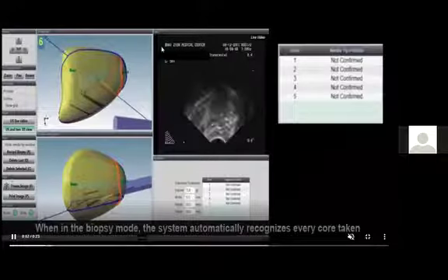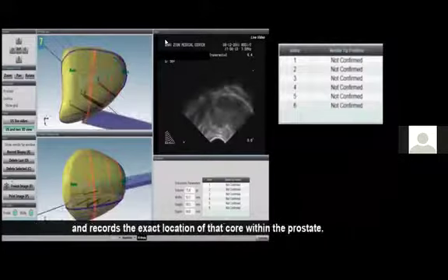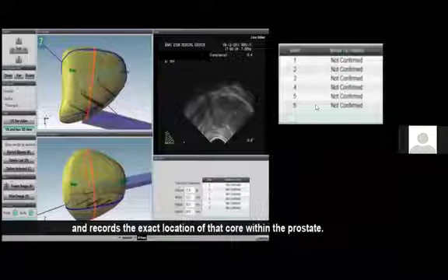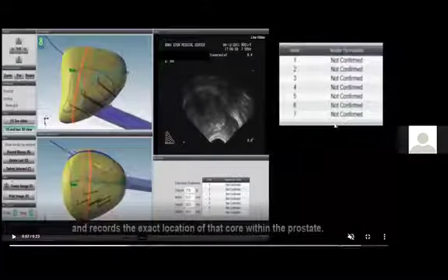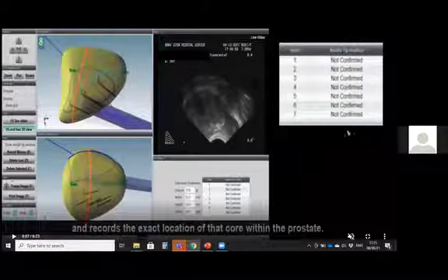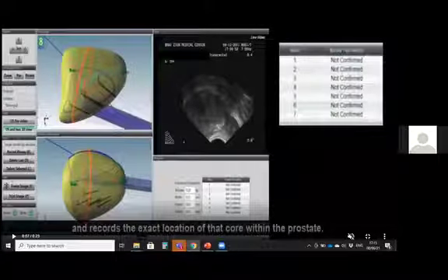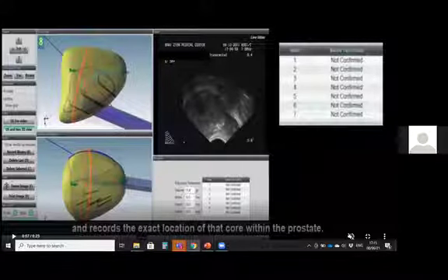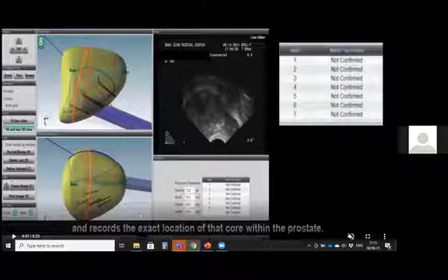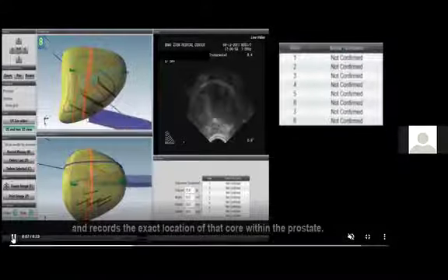It also included differential correction of patient movement during the procedure through a 6 degrees of freedom sensor attached to the back of the patient. Fusion algorithms allow for non-rigid registration between the modalities, compensating for shape deformations that often occur during the biopsy.